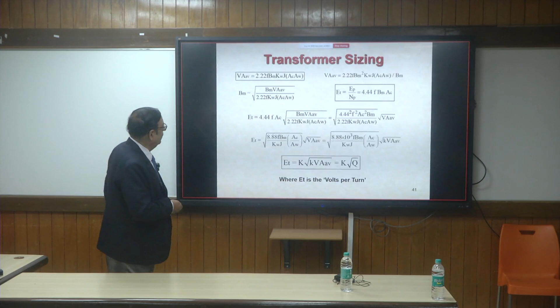Primary and secondary VA need not be the same in any application. It depends, because that's not the way VA is defined. The power transferred from primary to secondary may be the same, but the VA rating of a transformer is decided by the RMS amperes and the RMS volts rating of each winding. Whether you are able to load it to the full extent or not decides its utilization. I'll give you an example.